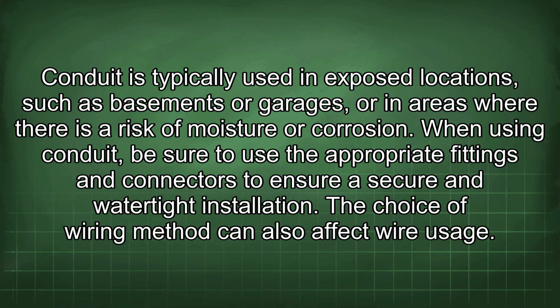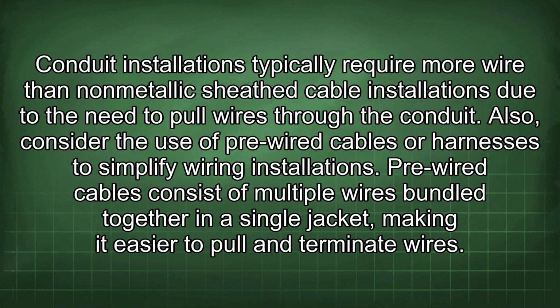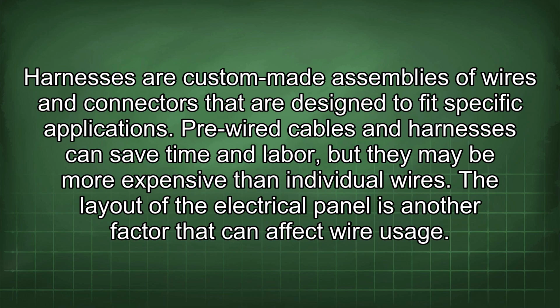The choice of wiring method can also affect wire usage. Conduit installations typically require more wire than non-metallic sheath cable installations due to the need to pull wires through the conduit. Also, consider the use of pre-wired cables or harnesses to simplify wiring installations. Pre-wired cables consist of multiple wires bundled together in a single jacket, making it easier to pull and terminate wires. Harnesses are custom-made assemblies of wires and connectors that are designed to fit specific applications. Pre-wired cables and harnesses can save time and labor, but they may be more expensive than individual wires.